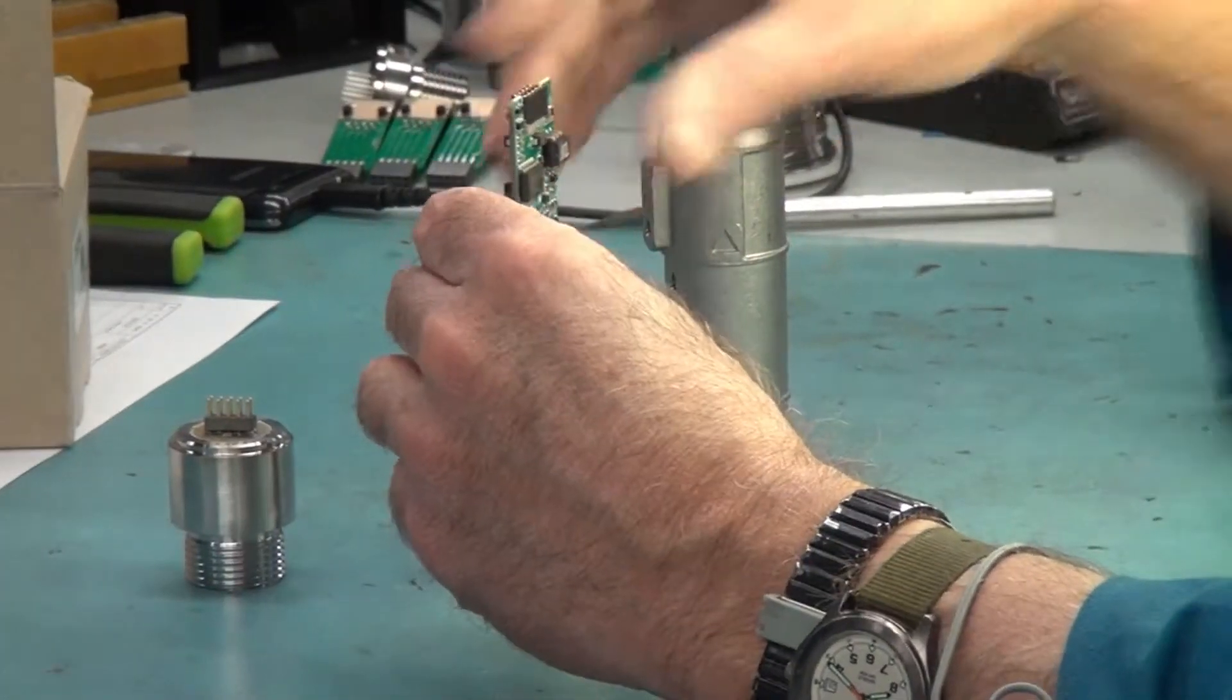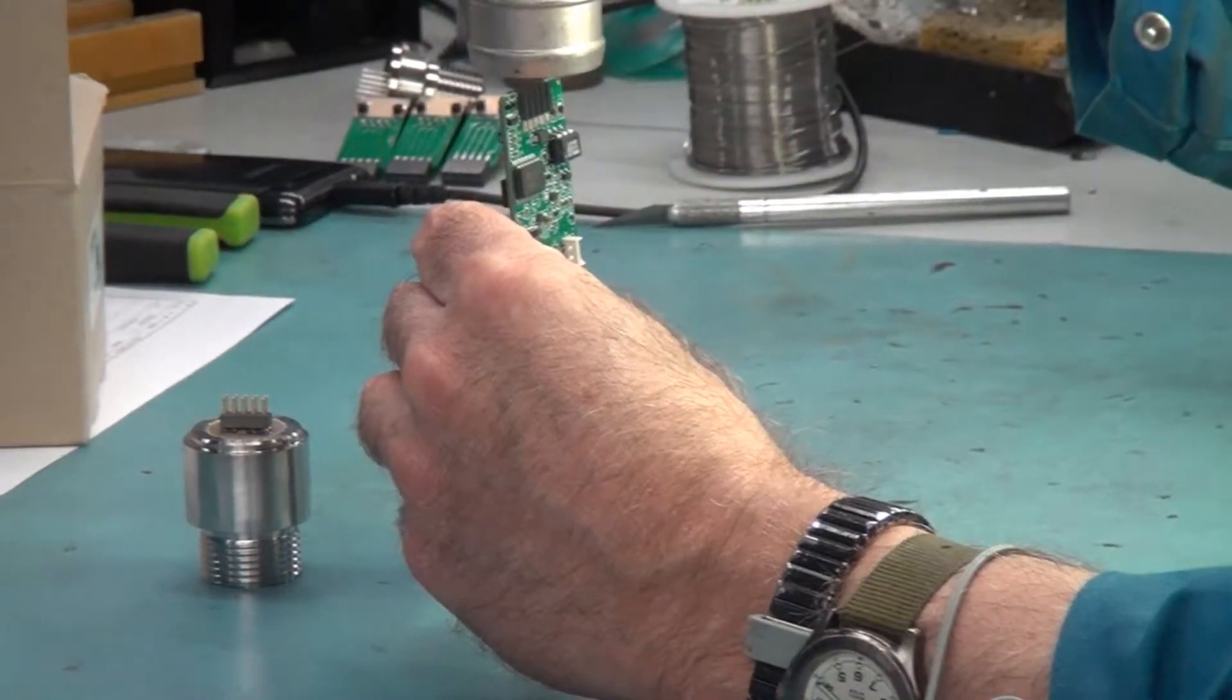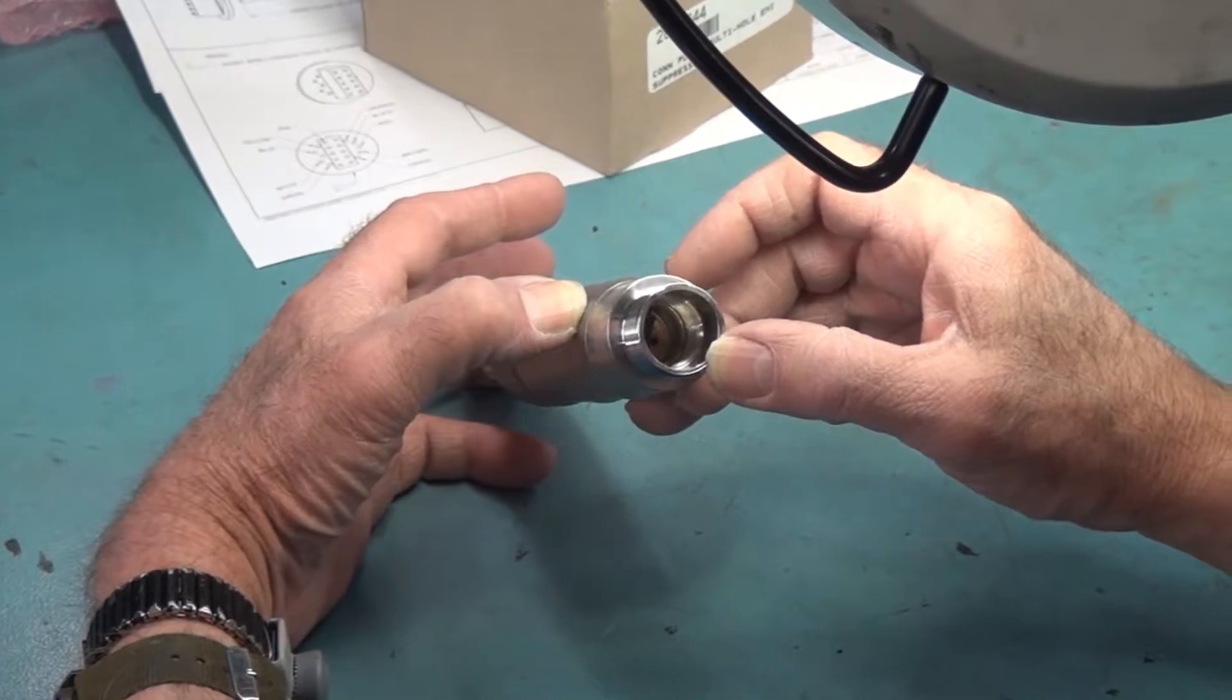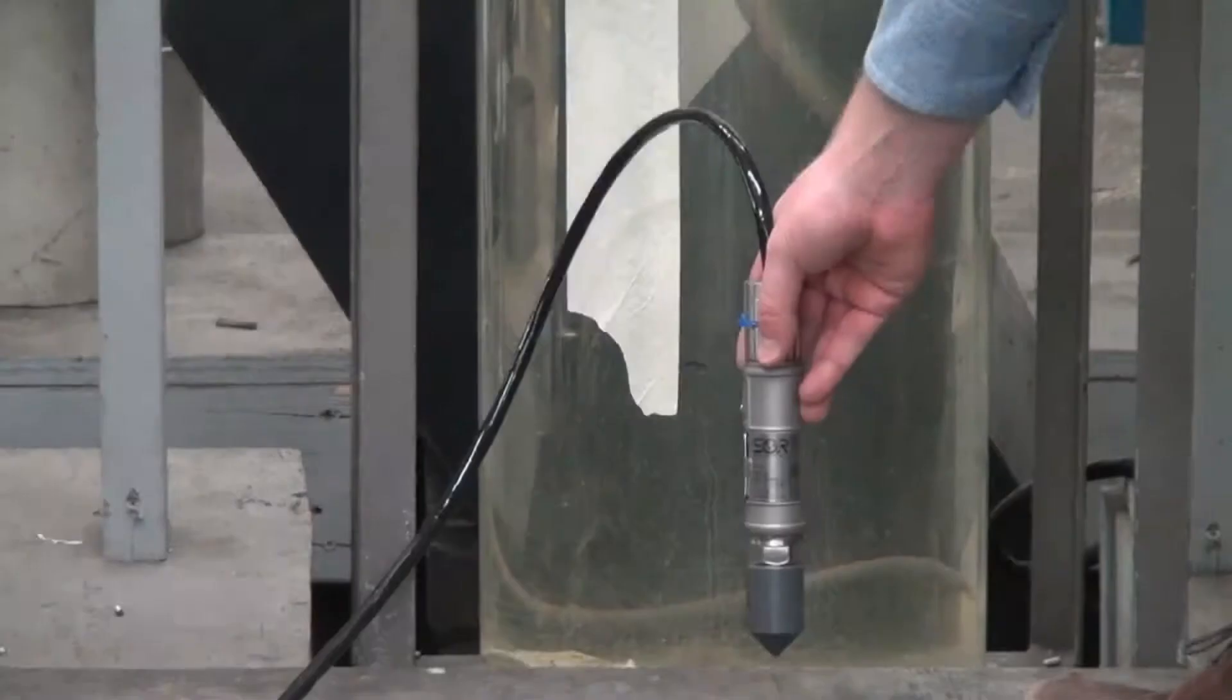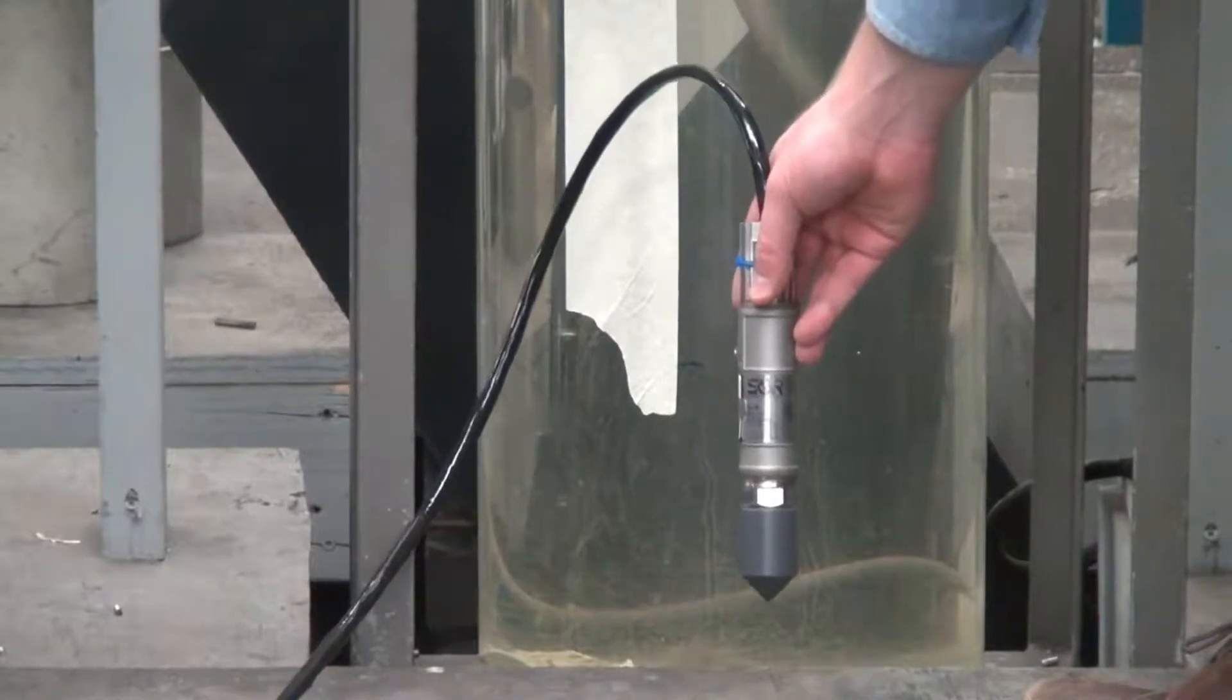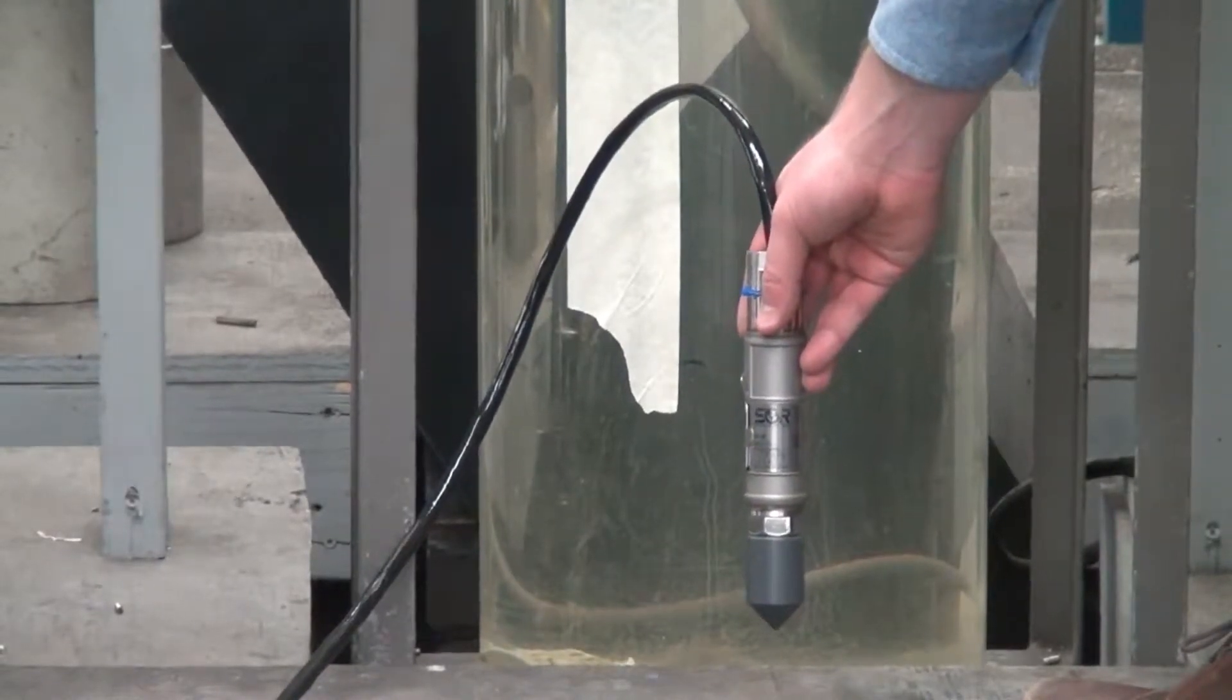The 815LT Submersible Level Transmitter is actually just a pressure transmitter. The way it works is it measures the hydrostatic pressure at the bottom of the tank. The point at which the level transmitter is at the bottom of the tank is the max height of the liquid level that you can measure.